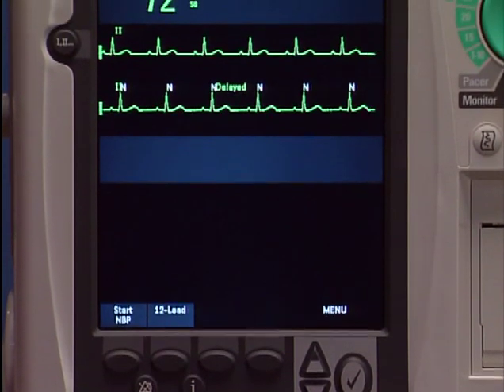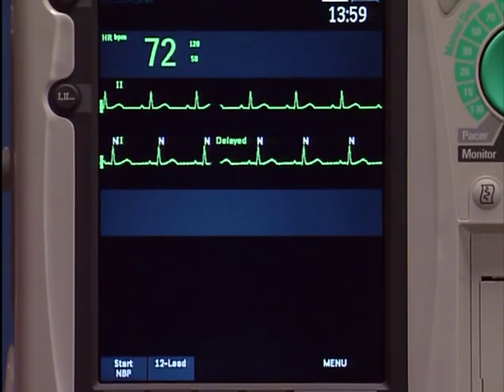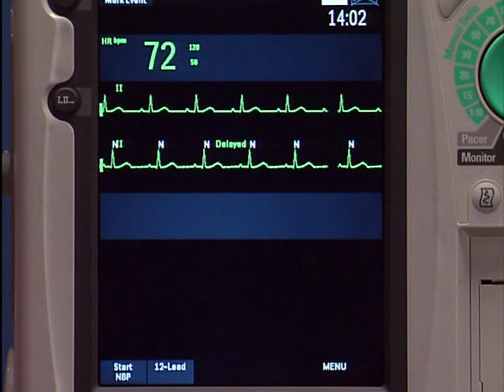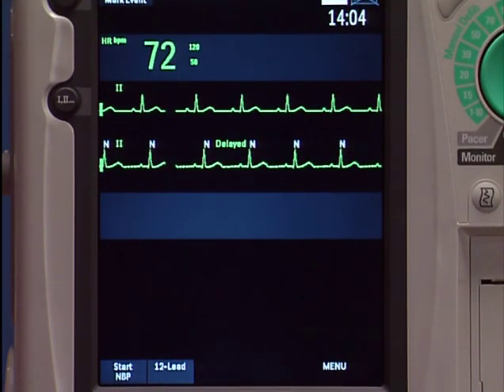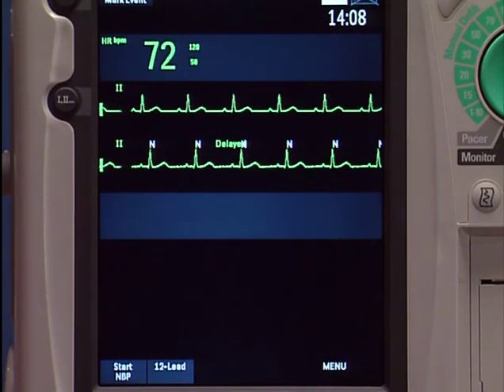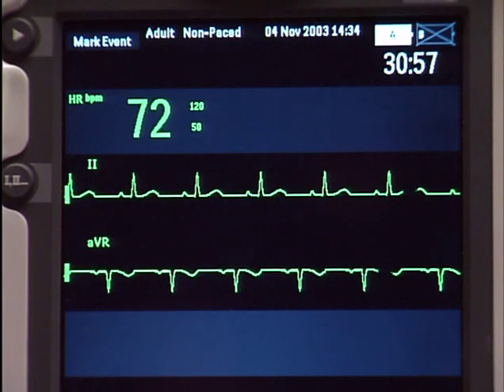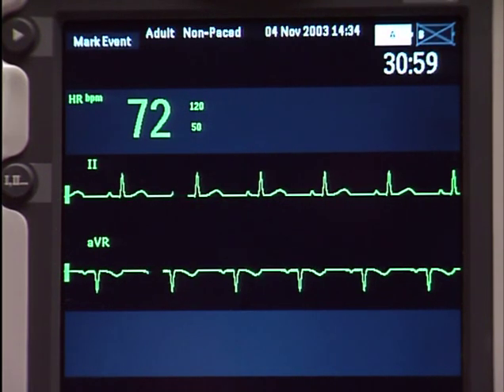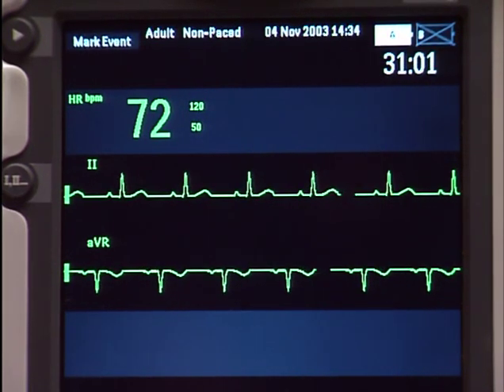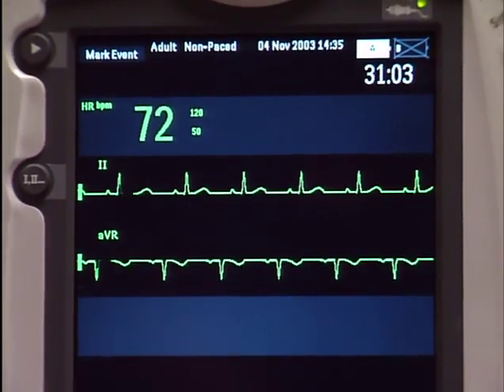The MRx uses the ST/AR basic arrhythmia algorithm for monitoring arrhythmia. It monitors pediatric and adult patients' ECGs for heart rate and ventricular arrhythmias and generates alarms. It specifically uses the ECG lead appearing in wave sector 1 for single-lead arrhythmia analysis. Note that increasing the wave size does not affect arrhythmia analysis.